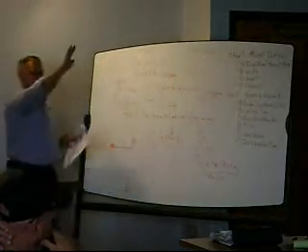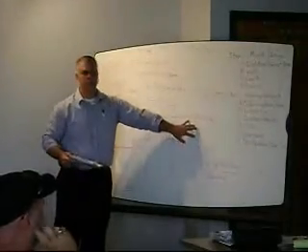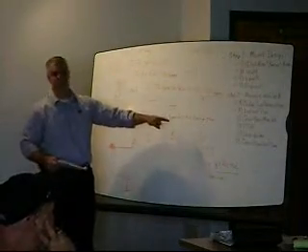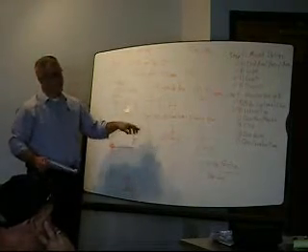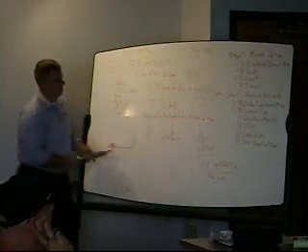That is, in this particular design, 12 feet. So he's pumping 12 feet uphill. So you can kind of see what elevation head is, taken pretty much one for one. 1 foot, you get 1 foot added to the TDH. 2 foot, 2 foot added to the TDH. Pipe losses are taken as equivalents. Okay? So to get TDH, we add this, this, this, and then that will give us a whole TDH.